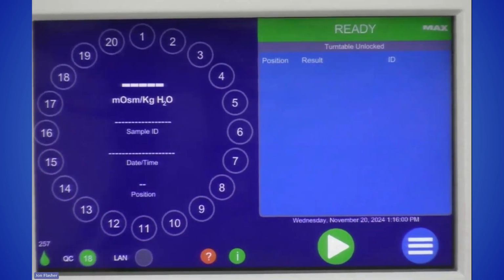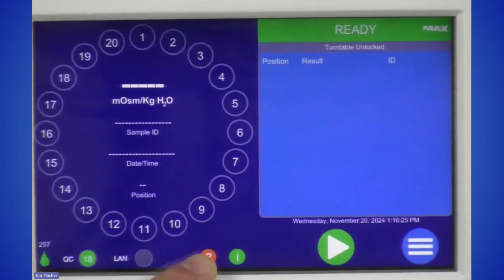This indicator here, where it says LAN, is going to be your LIS connectivity indicator. This is a demo instrument. I don't have an LIS here in the demo room in Norwood, so it's not showing anything. But typically, it's green if it's connected, and if it's not connected, it's red, and there will be a number in there that lets you know the number of results that have reported on the instrument that have not crossed over into your LIS. So that's also a helpful indicator.